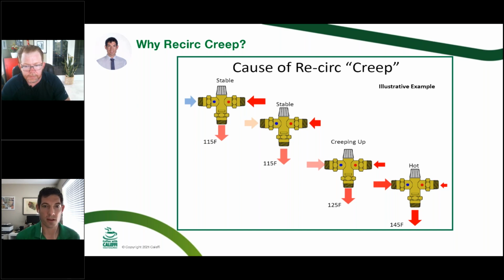The outlet's 115. So let's say it's starting to get later in the day. Maybe there aren't as many people that are using the fixtures. We're starting to lose some of that demand, and then creeping up on the third one, we are sending 125 out, but we're not really shedding any of that. And especially if it's a well-insulated line like it should be, we're not getting ice cold water coming back into the port. So we're not mixing that whatever it may have been 50-degree Fahrenheit water on the left anymore. We're starting to get 123 back or something like that, a warmer temperature.